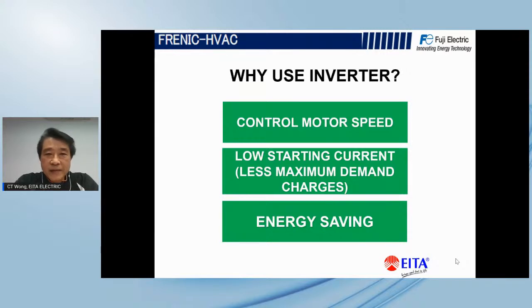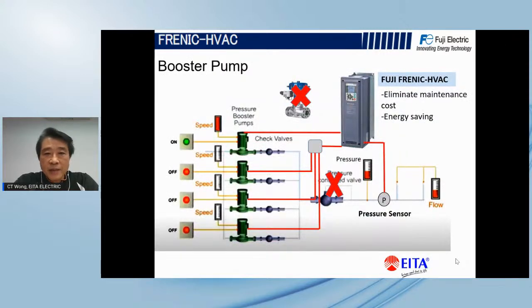So please remember that. A booster pump, in those days, was controlled by an on-off pressure switch, or, a little more advanced, by a control valve. But today you can remove the control valve and control by the inverters.